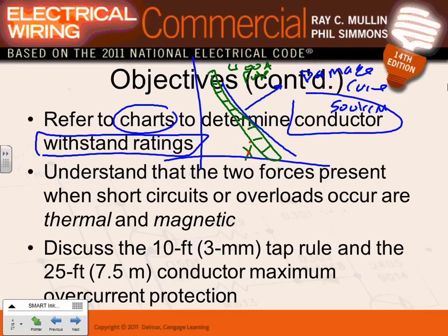Now we hit the fuse. What do you think when you hit the fuse? The fuse is going to start opening. Right at this point here, the fuse is going to start opening. By the time it hits the blue, the fuse will be what? Completely open, which means the damage curve has not been touched. My conductor will not smoke.